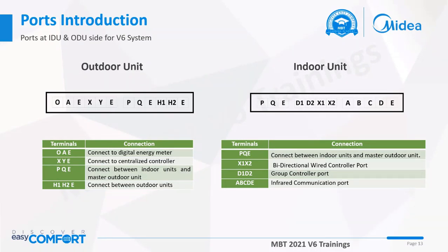On the indoor unit side, if you are using the old generation outdoor units like V5X or V4 Plus platform, there is quite a difference in the ports available on the outdoor unit and indoor unit. For V4 Plus or V5X, we used to have K1, K2E on the outdoor unit side, but that has been deleted now, and the information is merged with XYE itself, so now we only have XYE. For the indoor unit, we have deleted the XYE port that was available there, and now we have X1, X2 and D1, D2 ports. ABCDE is basically the display board, and PQE is for connecting to the outdoor unit side.